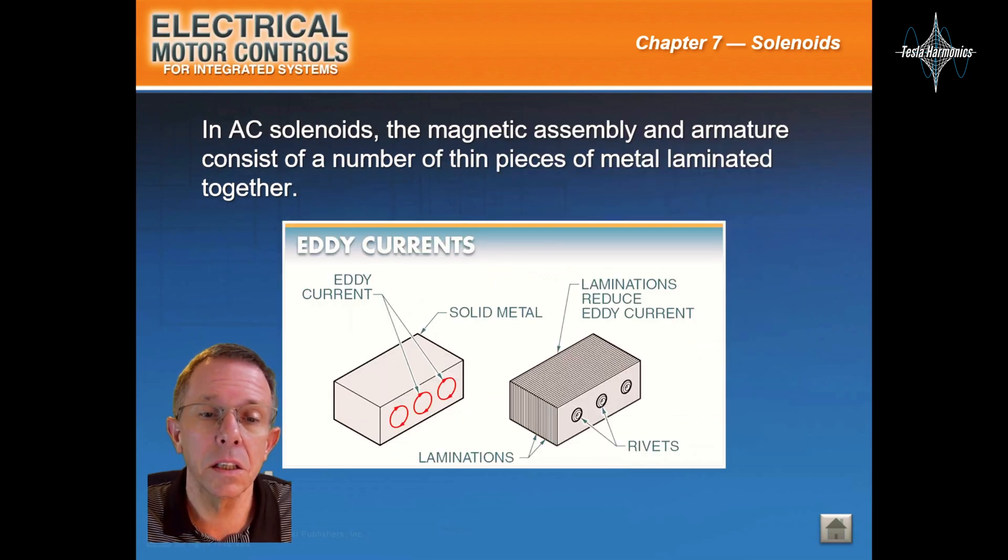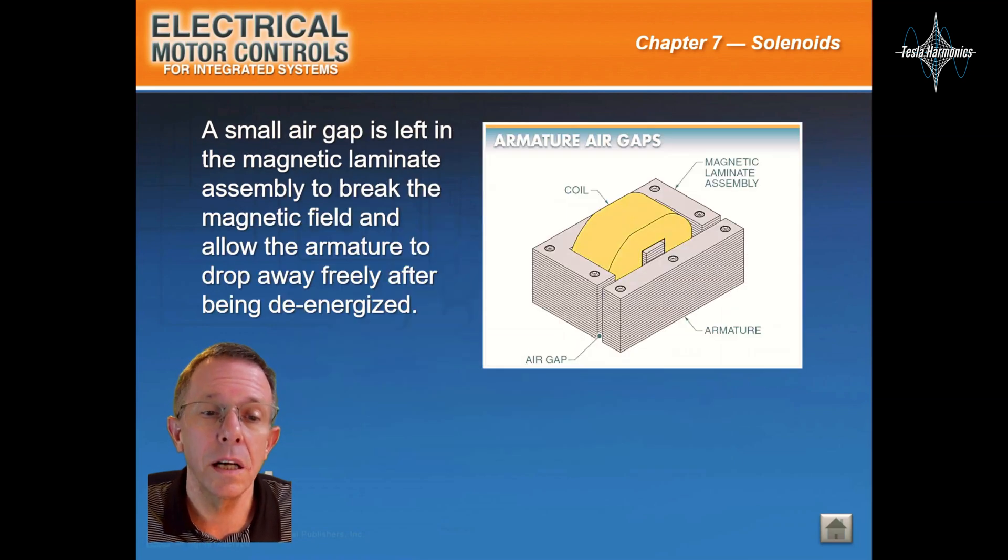In AC solenoids, the magnetic assembly and armature consists of a number of thin pieces of metal laminated together. A small air gap is left in the magnetic laminate assembly to break the magnetic field and allow the armature to drop away freely after being de-energized.